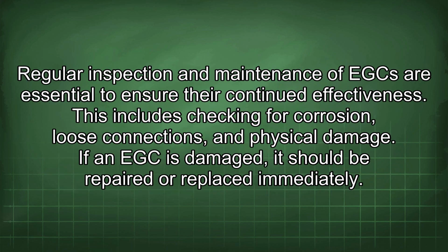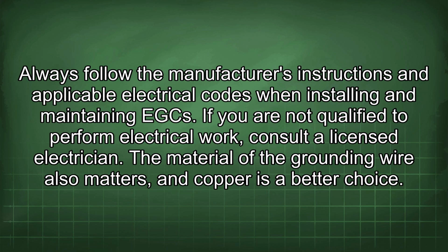Regular inspection and maintenance of EGCs are essential to ensure their continued effectiveness. This includes checking for corrosion, loose connections, and physical damage. If an EGC is damaged, it should be repaired or replaced immediately. Always follow the manufacturer's instructions and applicable electrical codes when installing and maintaining EGCs. If you are not qualified to perform electrical work, consult a licensed electrician.